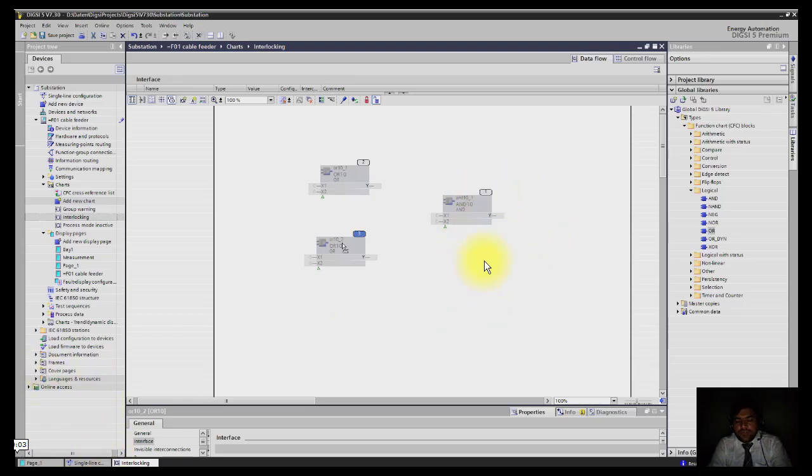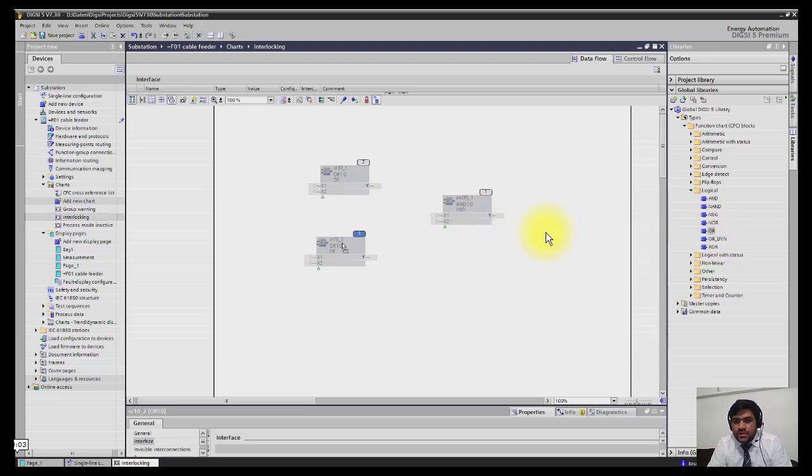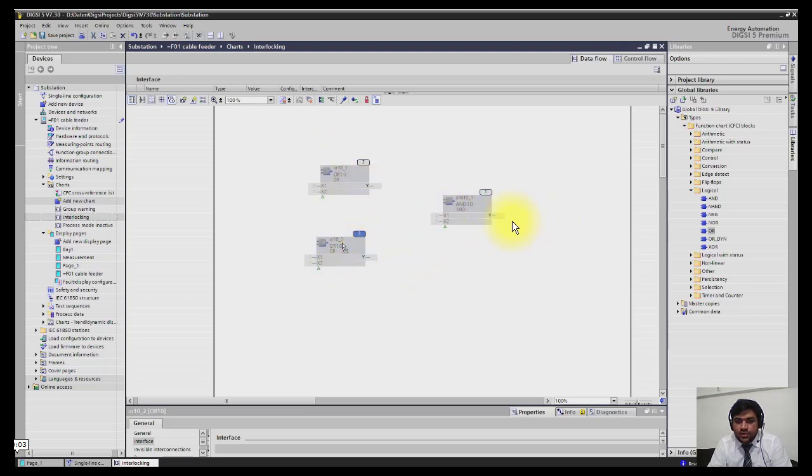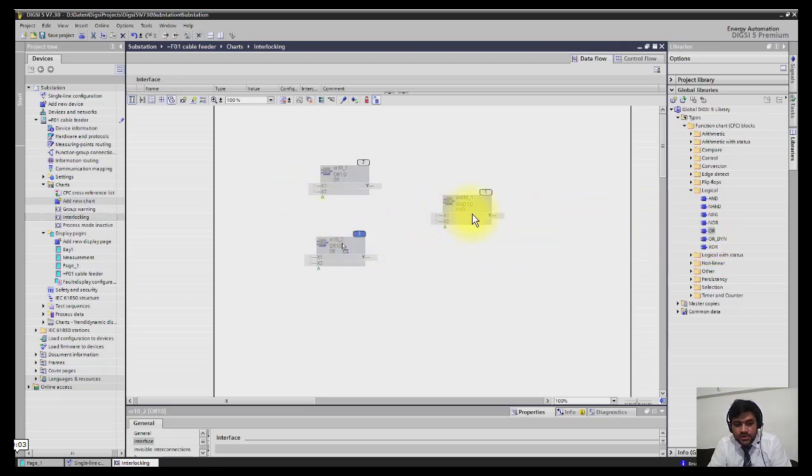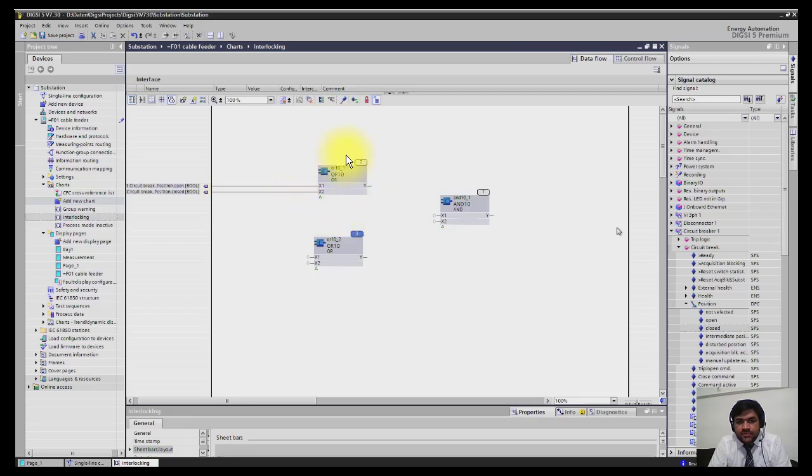Let's draw here the logic for the breaker. The breaker could only be operated if the isolator position is valid and the breaker position is valid. So first of all we have to choose AND gate, one for isolator, one for breaker. If both have valid position then it should enable the operation of breaker. I have to drag OR gates here, two AND gates.